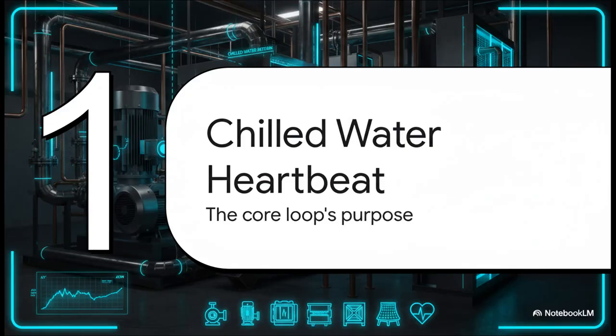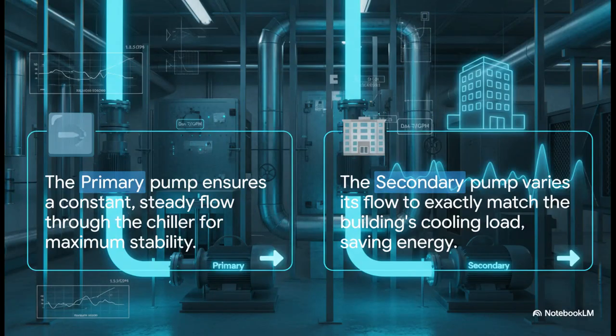So, at its core, this whole system is really just one big, continuous loop. The chilled water pumps are the muscle, the engine that pushes cold water from a central chiller plant all the way out to the equipment that cools the air. We're talking about those big air handling units, or AHUs, and the smaller fan coil units, FCUs. The pump's job is actually pretty simple. Push the cold water out, let it absorb the heat, and then bring that warm water right back to get chilled all over again.